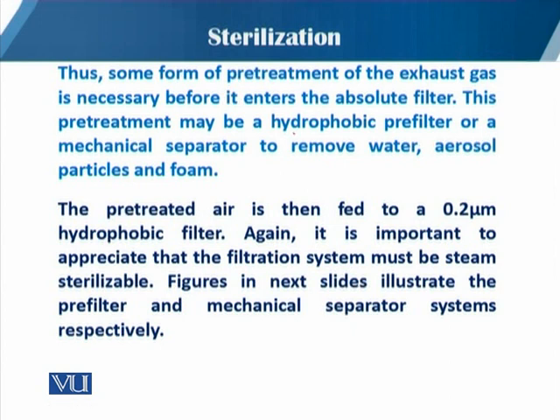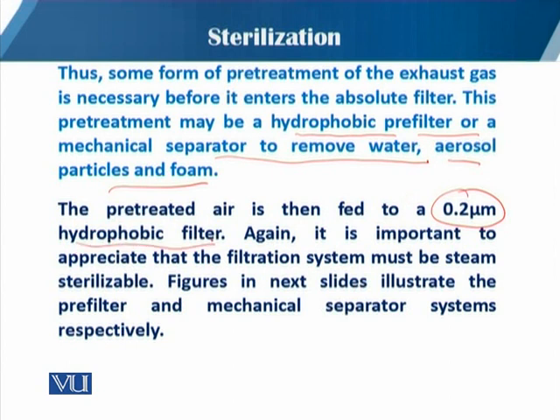This pre-treatment may involve hydrophobic pre-filters or a mechanical separator to remove water aerosol particles and foam. The pre-treated air is then fed into a 0.2 micron hydrophobic PTFE filter. It is important to note that the filtration system must be steam sterilized, including both the inlet and the outlet.